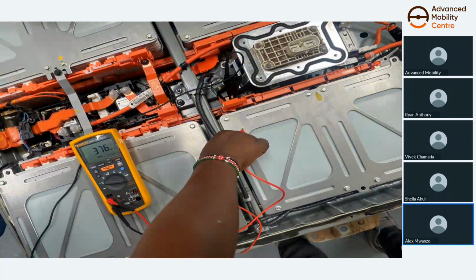So we're using a fluke meter, and anything above 300 ohms is acceptable. Anything below that means it's shorting to ground. So all the necessary precautions have been taken. Our floor is electrostatically insulated, and we also have electrostatic mats on the other side that we normally stand on when working on it. I'll have a picture of that at some point.